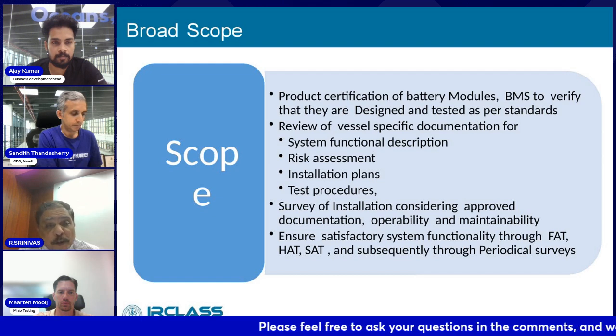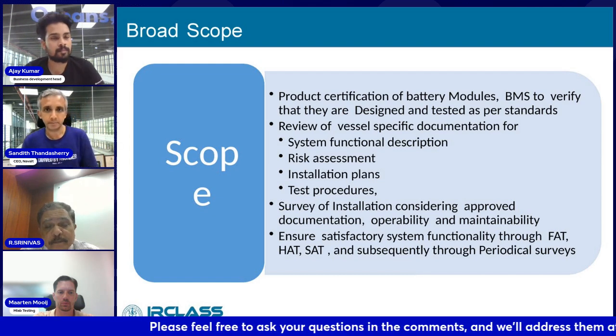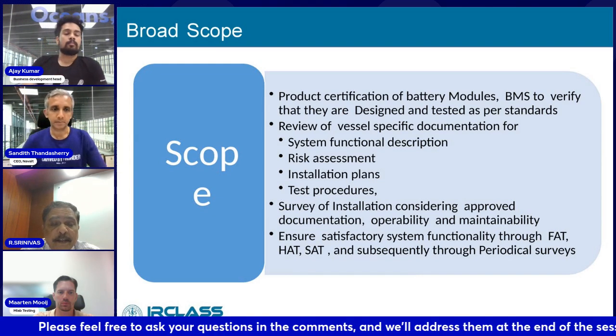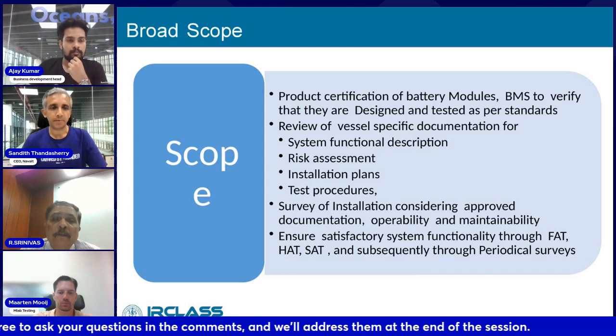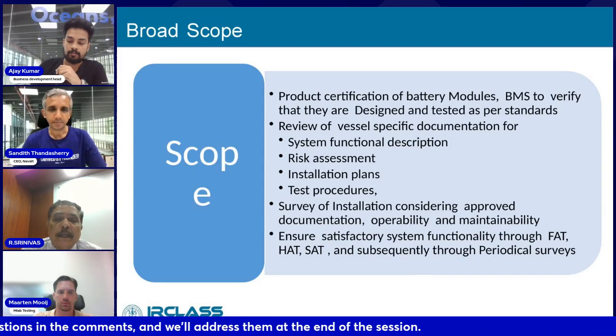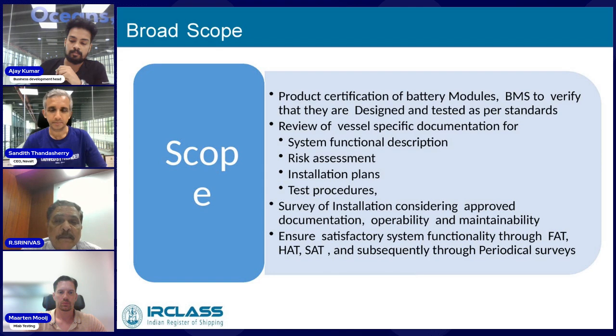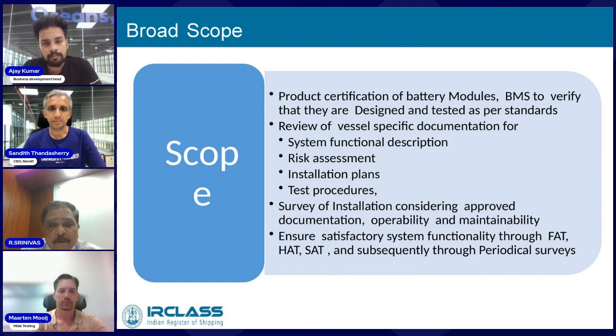Now, to ensure that these things are done properly, or at least to verify that they have been addressed, we look at our scope. We start by looking at the product certificates of the battery modules and the BMS, the battery management system, because to prevent overheating, undercharging, and overcharging, a proper BMS is very essential. So the BMS becomes one of the most important safety factors, not only from the perspective of charging the batteries, but maintaining the safety of it.